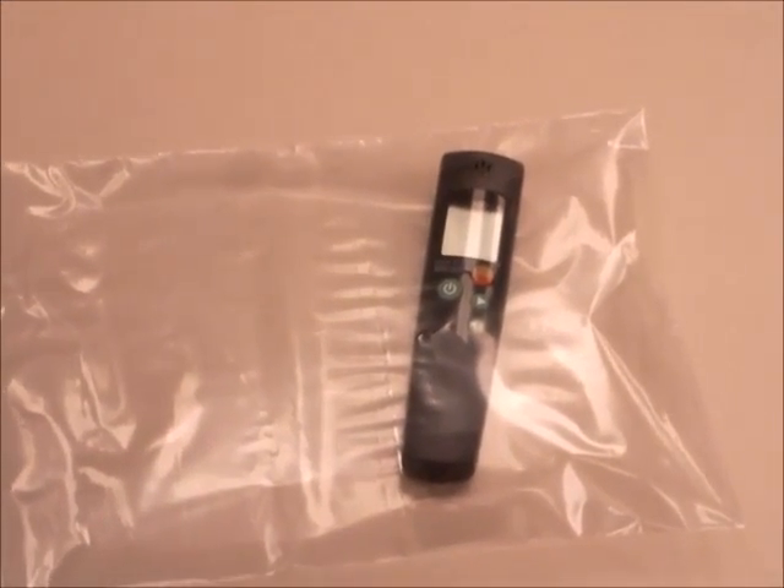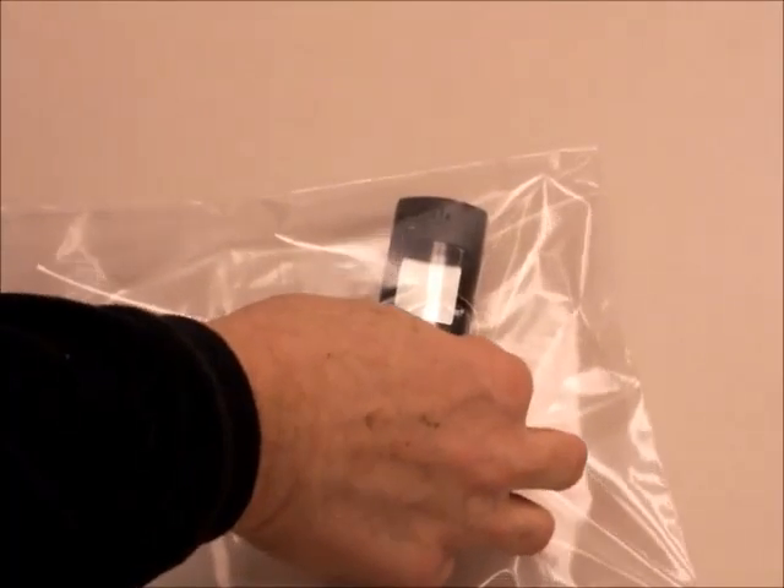We have a 317 in a plastic ziplock bag and it's got CO calibration gas in it. So by simply turning it on it should alarm even when it's in a room that's contaminated.